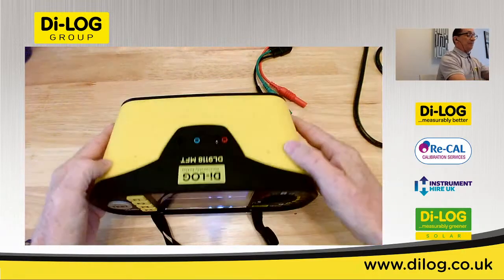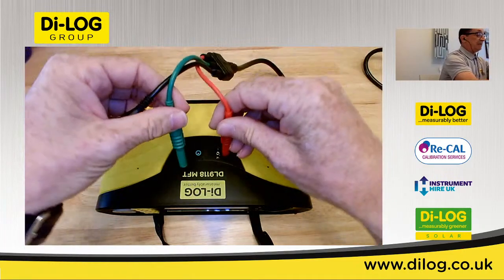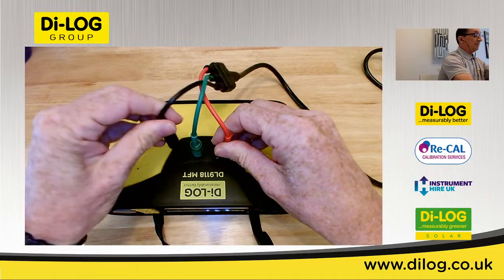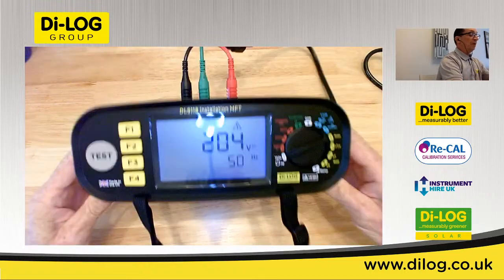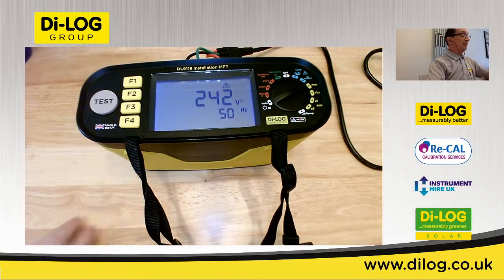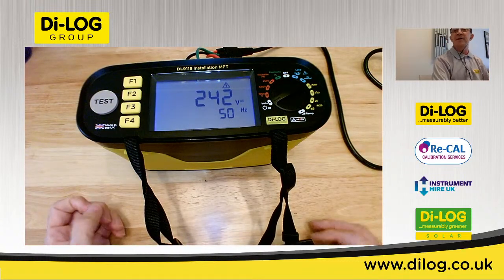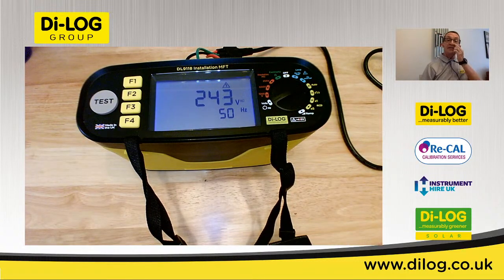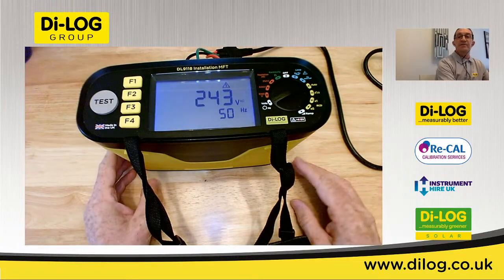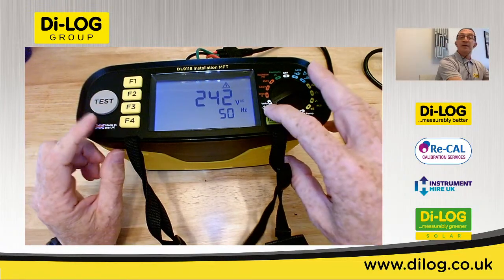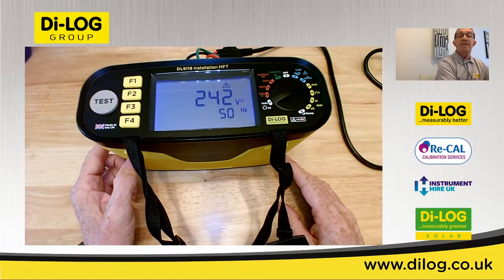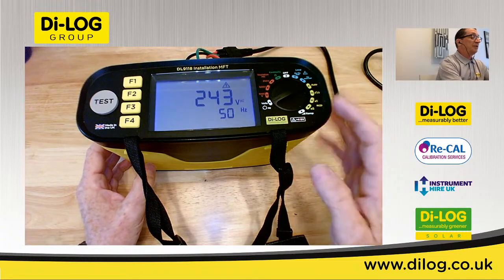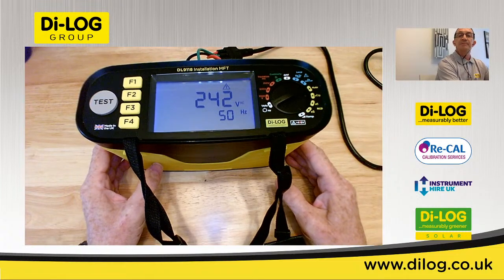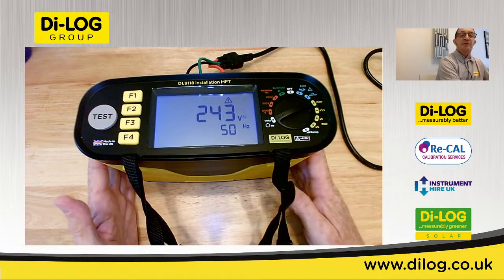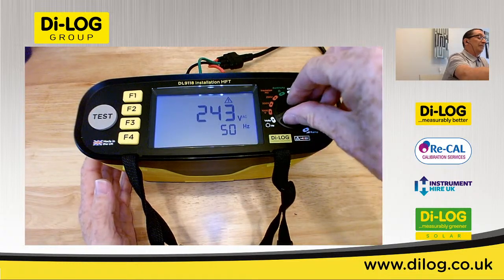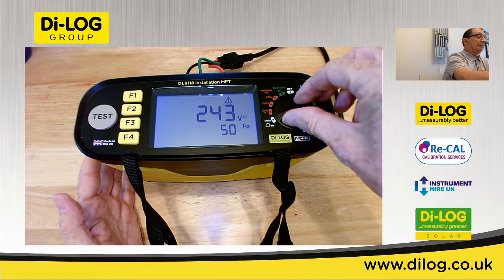Switching back past 1000 volts and back to voltage. This is also where, on this particular model, the three-phase indication will be given if L1, L2 and L3 test leads are connected to three-phase voltage. You can see the symbol in the corner of the display there. But on that you've also got your voltage and your frequency display. So a nice big clear display, very clear, no matter what environment you're working in.